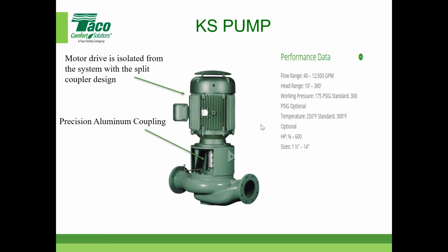When I talk alignment, I'm talking about the motor shaft and the impeller shaft - there are two actual shafts that meet up, and they have to be within alignment of 5 thousandths on base mounted pumps. Here, we don't have to worry about that. You don't have to call in that alignment guy that brings in his machine to align it. Something to be considered.